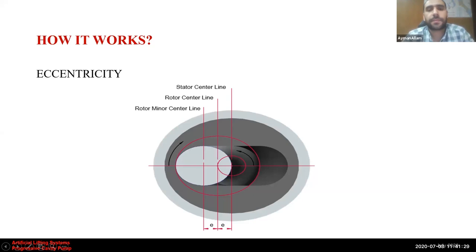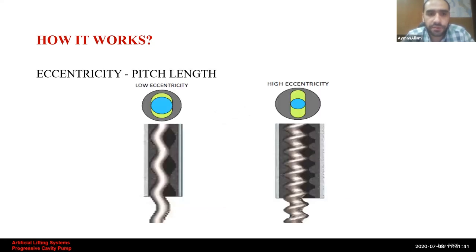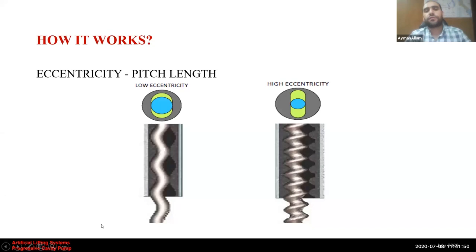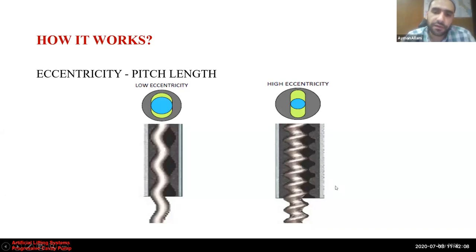Pumps with low eccentricity and long stator pitch are more suitable for pumping higher API, lower viscosity, and higher water cut fluids. Pumps with high eccentricity and small pitch length are more suitable for pumping high-viscosity fluids and high sand content.